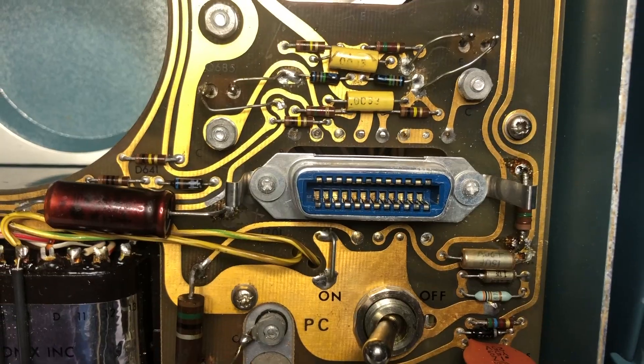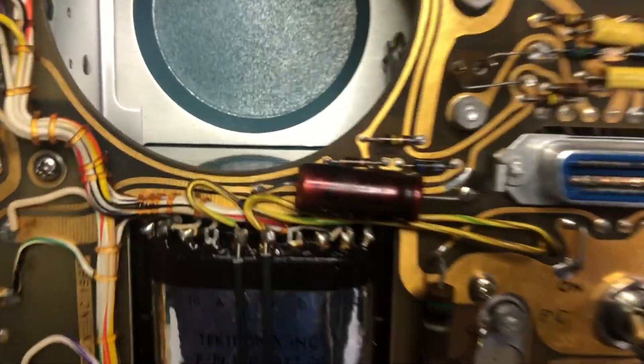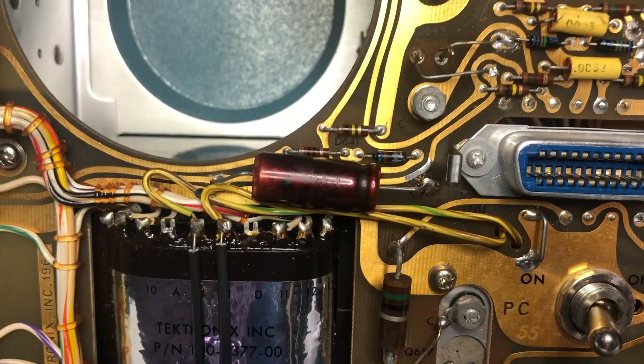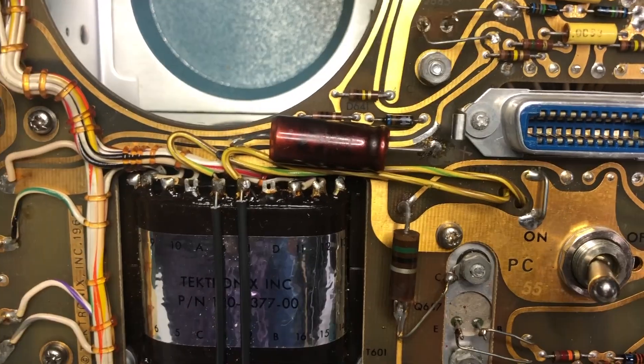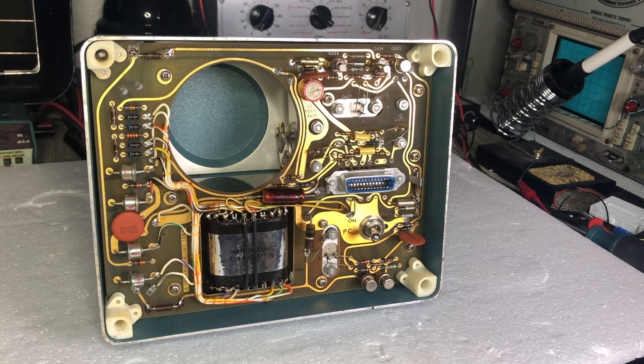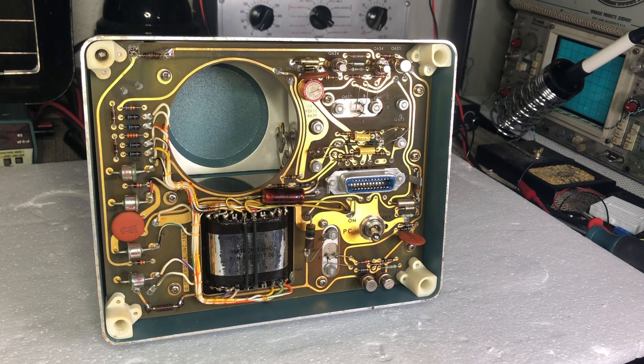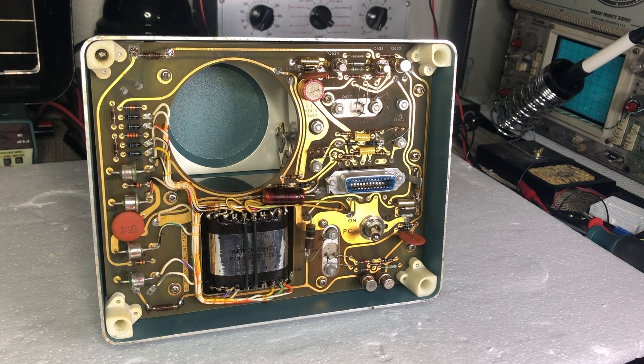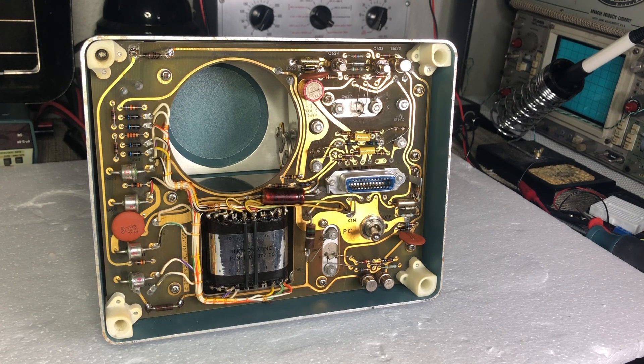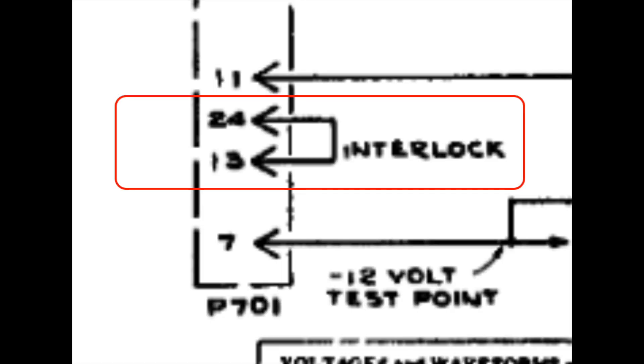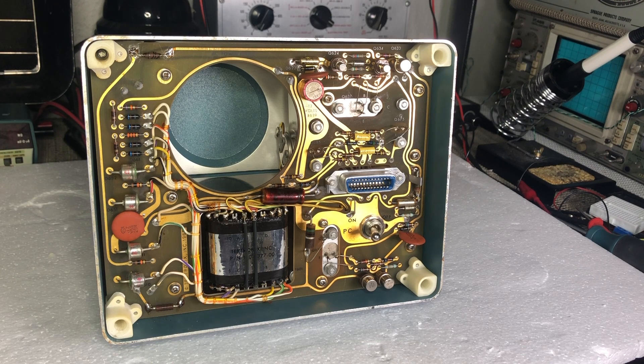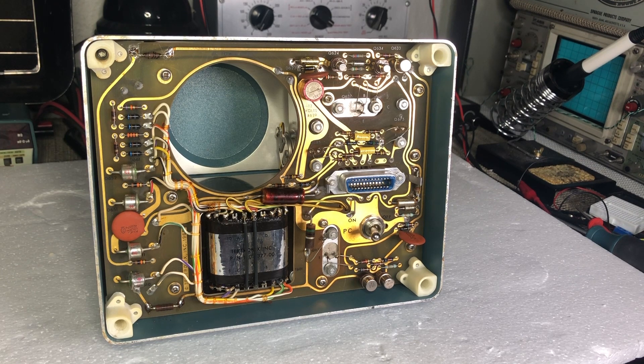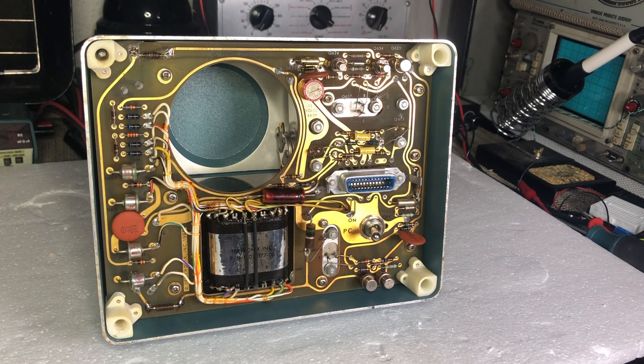This is the actual power switch in the power supply module, and that's a connector on the power supply side. Oh, I can already see something—a capacitor which is probably suffering a little bit of overheat or maybe bad. Like the 555, you cannot power on the power supply unit just by itself because they have an interlock jumper on the indicator unit which feeds the main power through the indicator unit and returns it back to the power supply, just to make sure you cannot turn on the power supply without a load. We can bypass it.